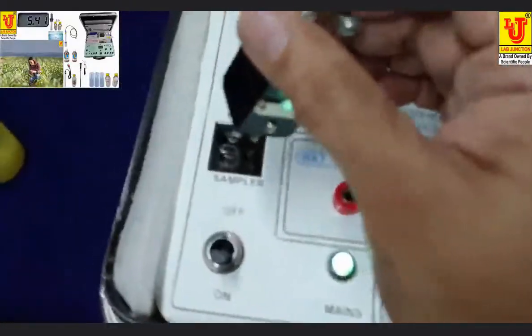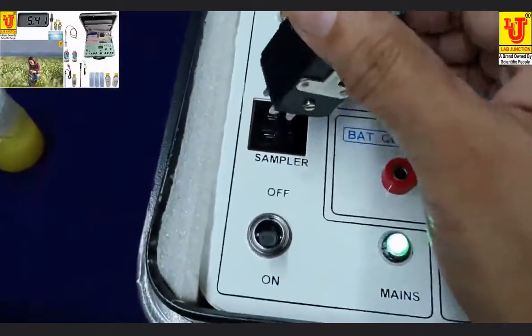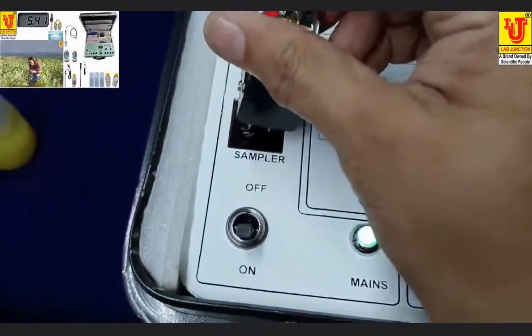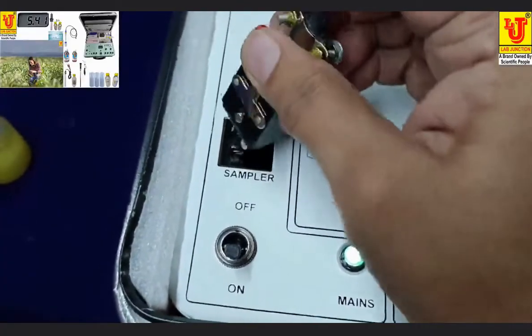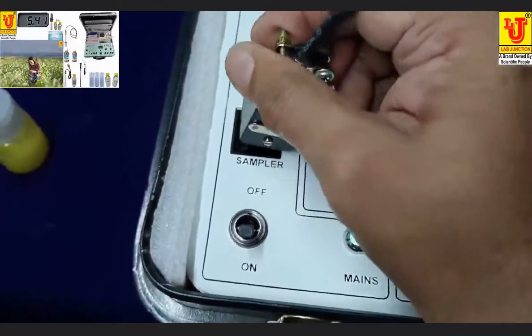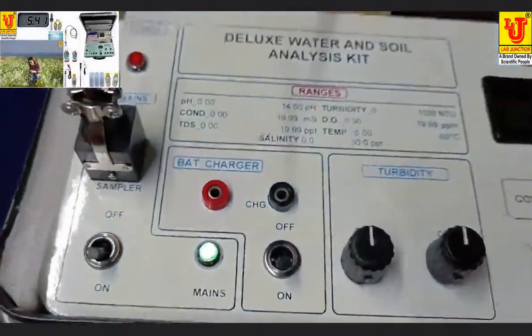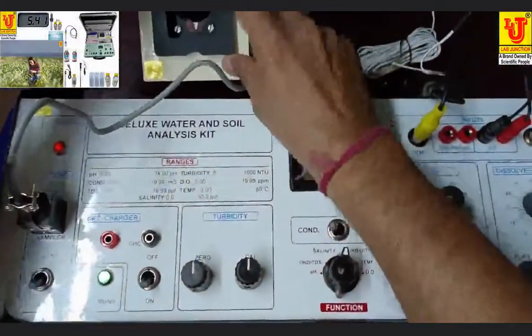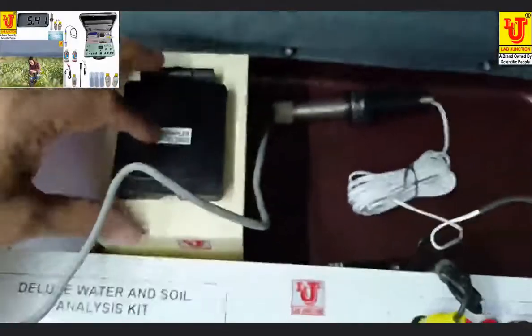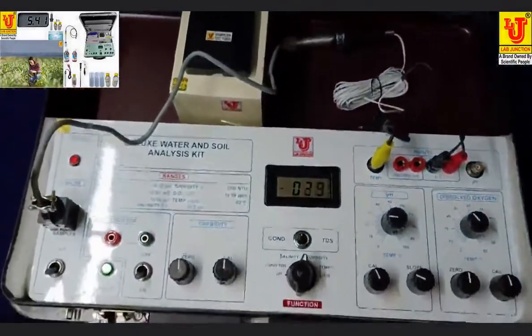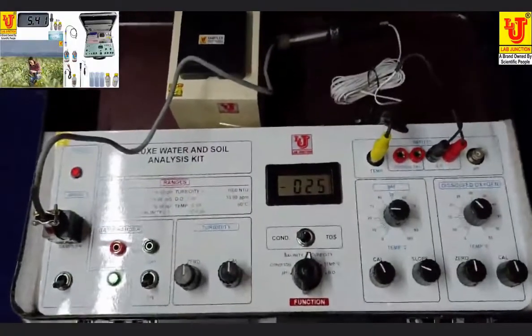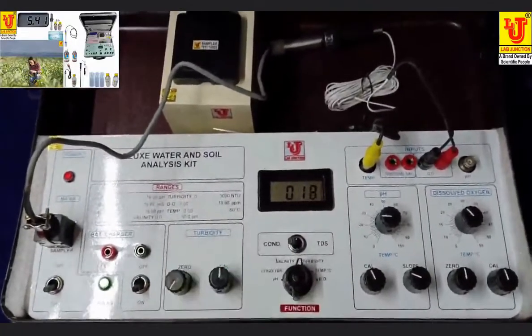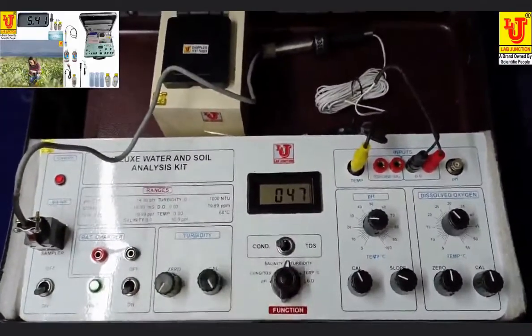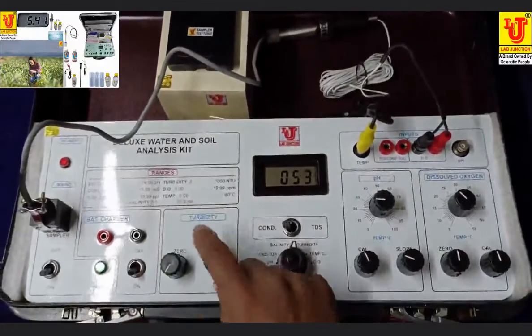Now connect this tube to this side, like this. Now your turbidity sampler is on. So how to test turbidity? First, you go to the turbidity control. First, set the zero control to minimum position and the cal control to maximum position. Zero control to minimum, cal control to maximum.